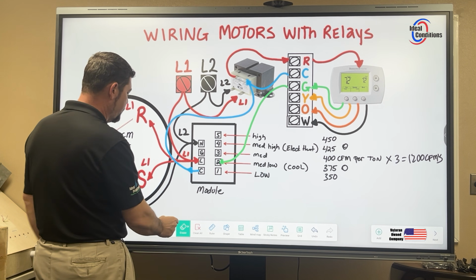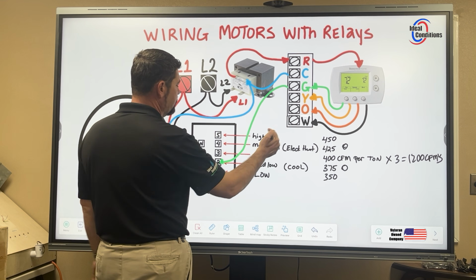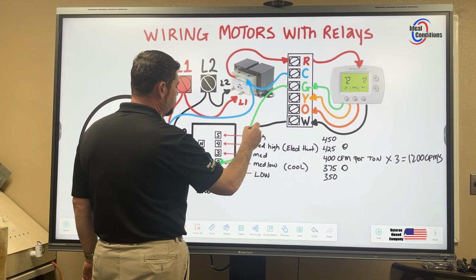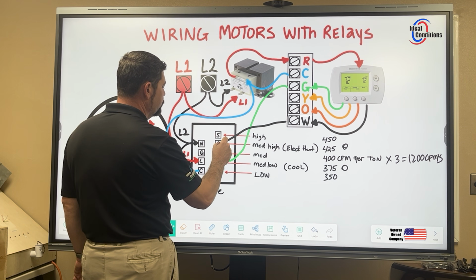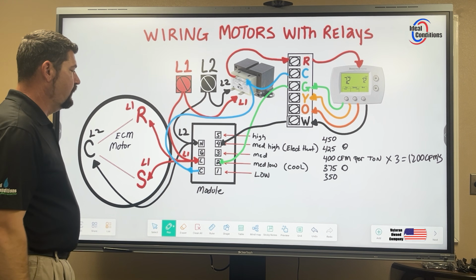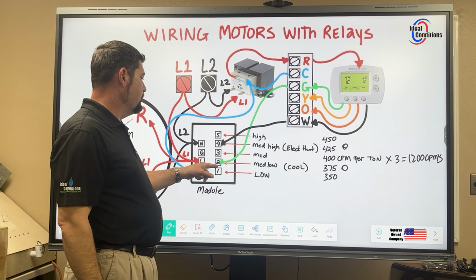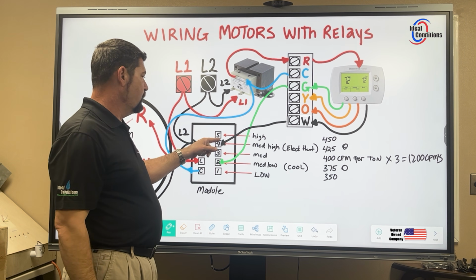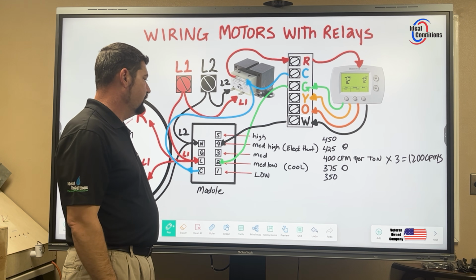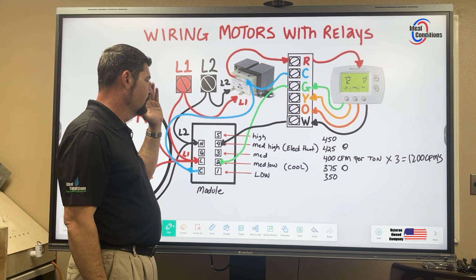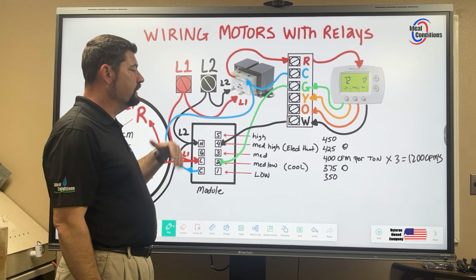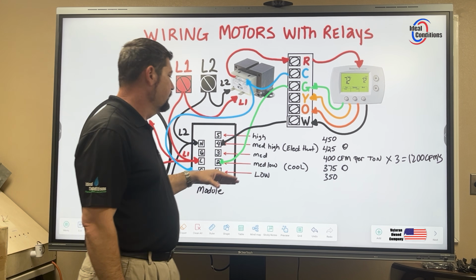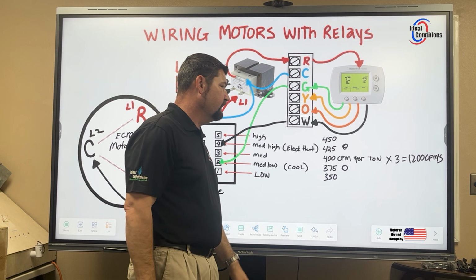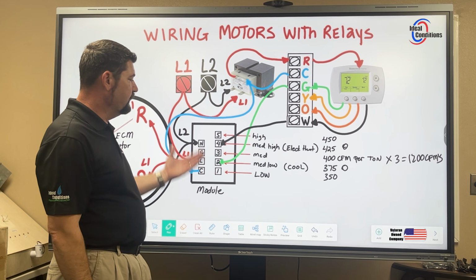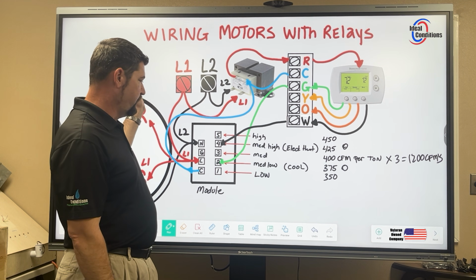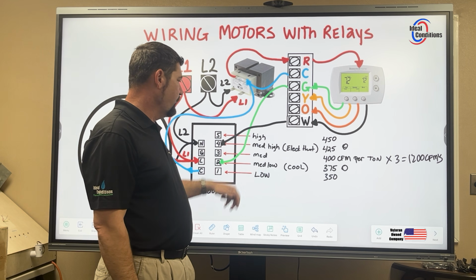In our diagram, what we're gonna do is we're gonna take our W and we're just gonna come out and we're gonna wire over to terminal 4. Now I can say that I want G to be terminal 3 and I want W to be 5. Okay, that's fine. I can run medium speed and high speed.